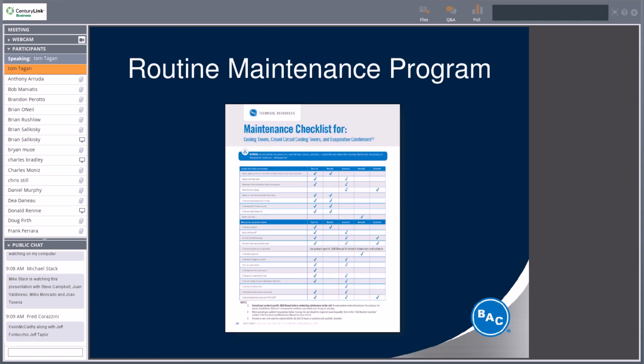So if you look at this maintenance checklist, the first line item, which you cannot see, basically is saying inspect the general condition of the unit and check for unusual noise or vibration. A lot of a cooling tower inspection is just a look and listen. When you're doing your routine maintenance and you're on the roof or you're near the cooling tower, just pause for a moment, take a look, make sure there aren't any leaks, any unusual noises. Obviously, if there's a leak, you should address it right away. Investigate whether it's possibly just a seam leaking or whether there's corrosion to the distribution basins or the collection basins.